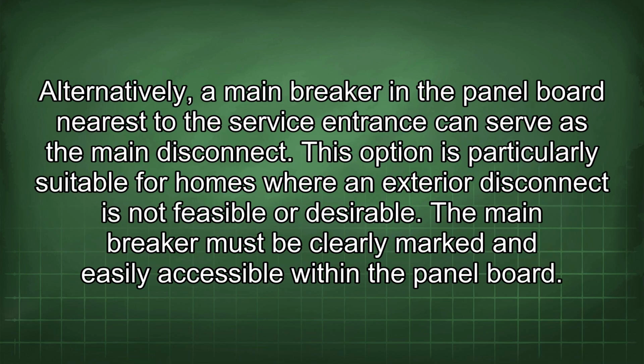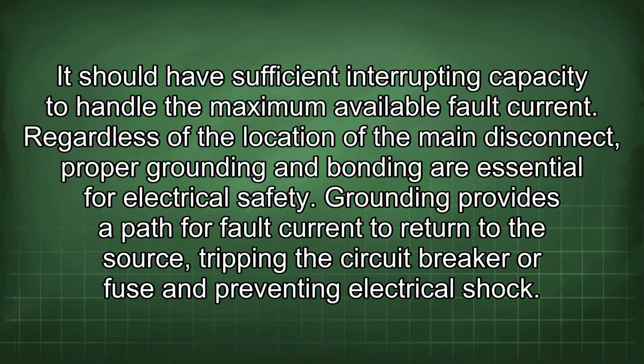Alternatively, a main breaker in the panel board nearest to the service entrance can serve as the main disconnect. This option is particularly suitable for homes where an exterior disconnect is not feasible or desirable. The main breaker must be clearly marked and easily accessible within the panel board. It should have sufficient interrupting capacity to handle the maximum available fault current.